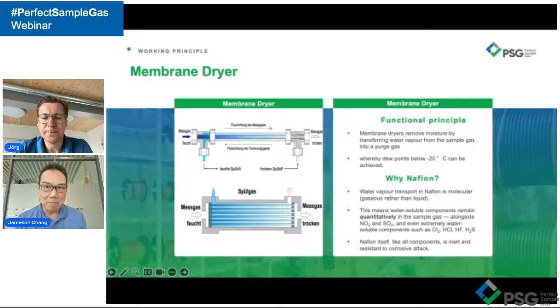Another option is that you can have our standard cooler. At the downstream, you add a membrane dryer, and you're able to bring the dew point of the sample below the SO3. Therefore, it actually eliminates the corrosion and also the interference in your measurement. Of course, for the Nafion to work, you need to have dry instrument air to pair them together. Yeah, that is required.